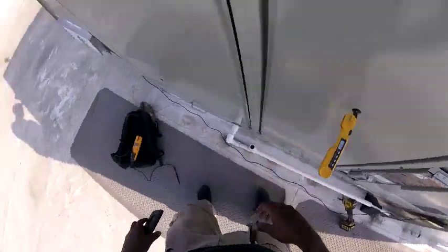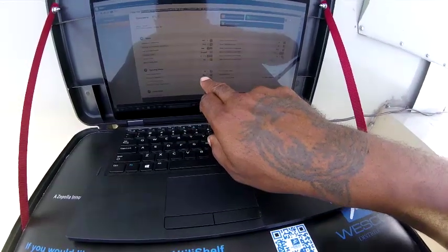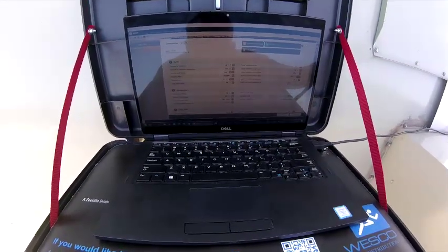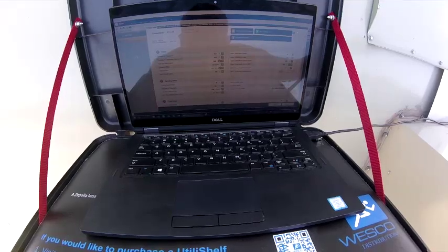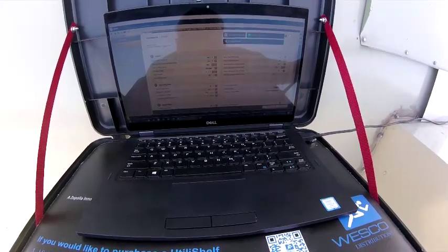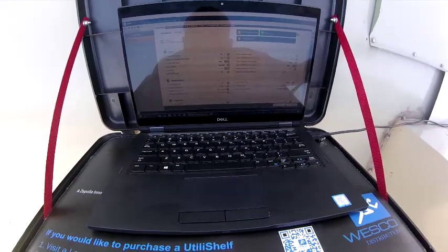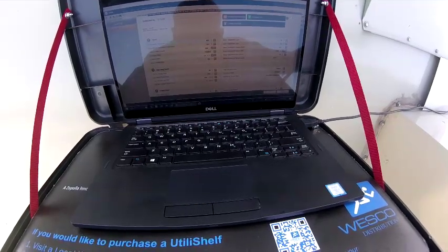Great day. That circuit one just came off. See if that discharge air temperature is going to drop. It seemed like it actually went up. I was at 58, now I'm at 59. It should start dropping. So the set point is 54. It seemed like circuit one kicked on when it was about 5 degrees above that set point. Starting to drop now. I'm at 58.